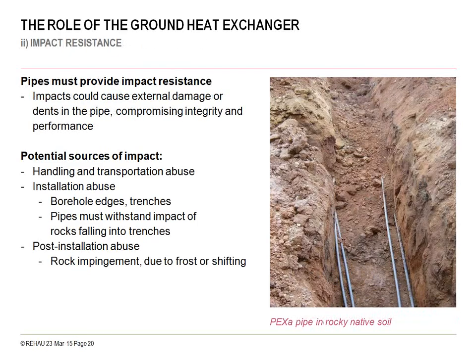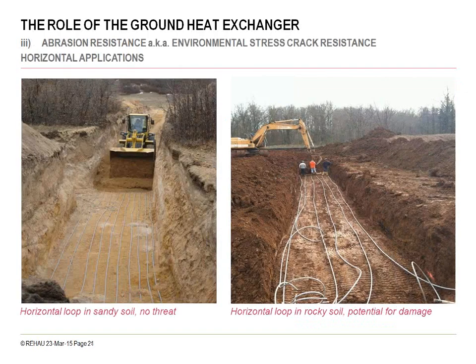Impact resistance is an important consideration, being that these piping systems are outside, in the earth, and we want to have a strong pipe material that can withstand some rocky soil conditions, as you see in this image here with PEX-A pipes. You want to have physical properties that can safeguard against impact and provide impact resistance and puncture load resistance. This is some images here with PEX-A pipes, and it's a little extreme, I know, on the left, but it's showing you the durability of PEX-A material in piping systems. As you can see, that heavy equipment, backfilling over the tops of the pipe with that heavy equipment.